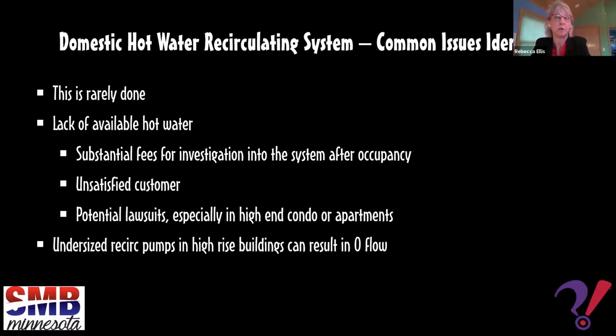But as soon as it cools down, the valve opens, will start to open maybe at 110 degrees Fahrenheit. And once it opens, it'll start letting the hot water flow until the riser fills up with hot water again. Those are very popular these days, and they're great for contractors because they work usually at the beginning.